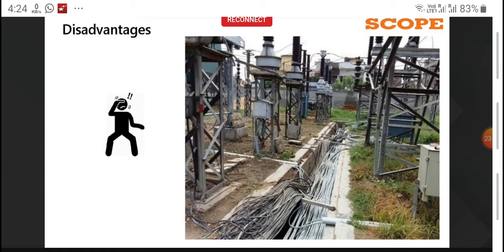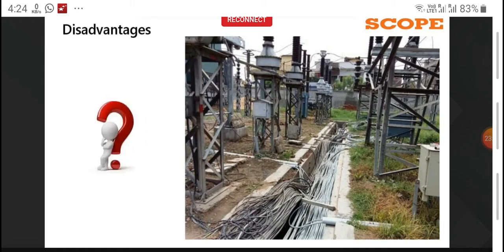Even if he wants to rectify it, it is very difficult, because there are so many damaged cables and he does not know what cable is carrying what. So this is the problem we are still facing in substation automation systems. This is the disadvantage of the substation automation system, where your substation is semi-automated: from the switchyard to the control room we are still using copper cable or a manual system, and from the relay and above we have mostly automated the system. This is the SAS-based substation we are talking about.